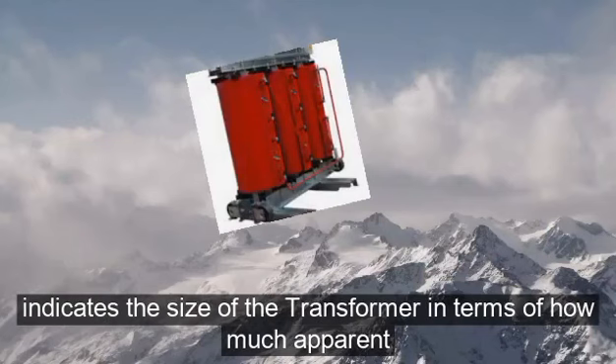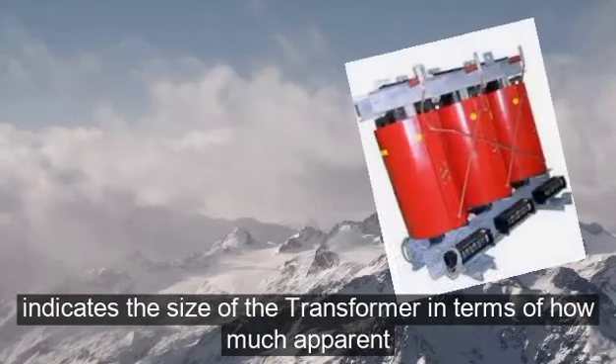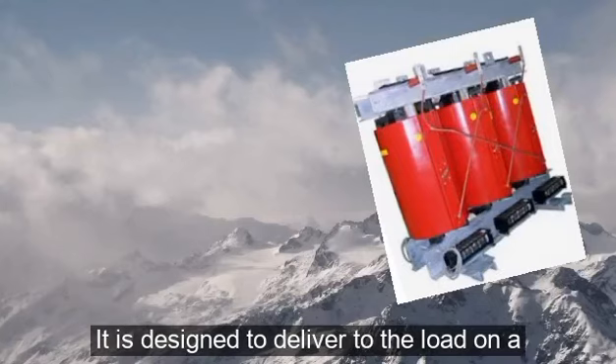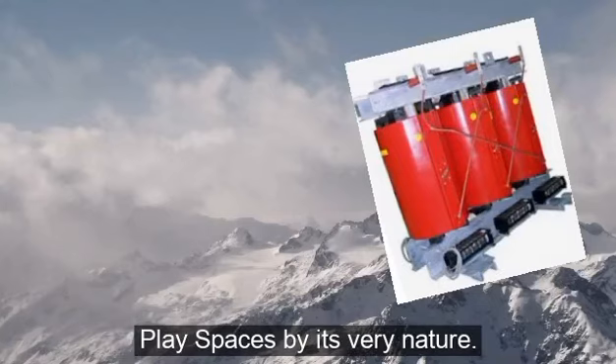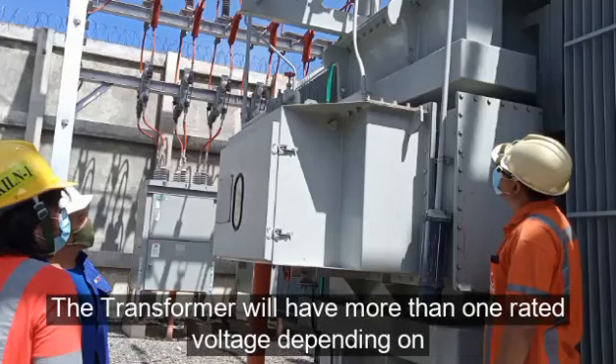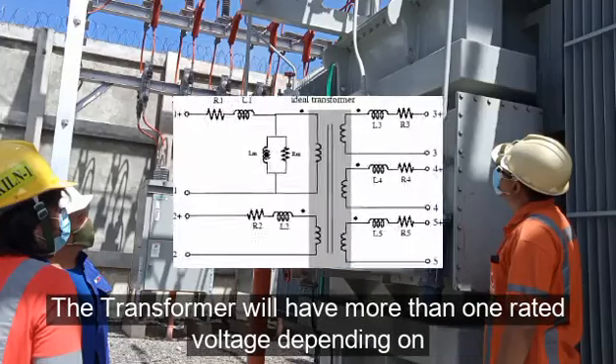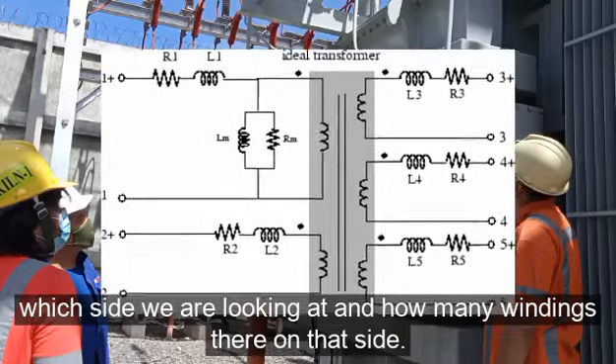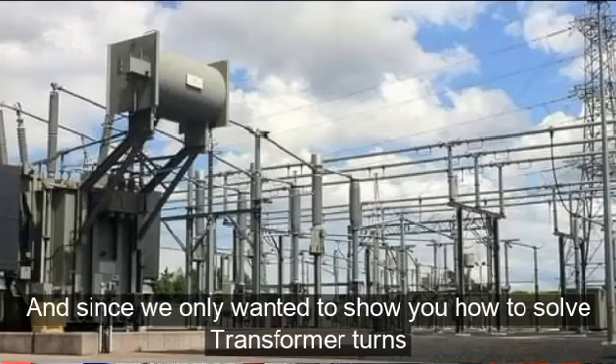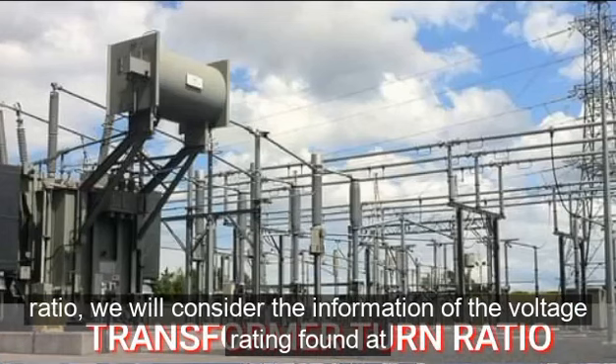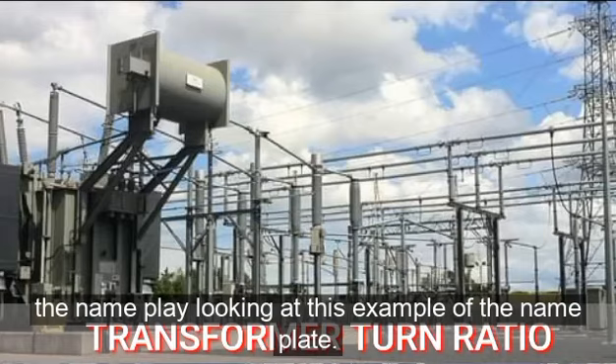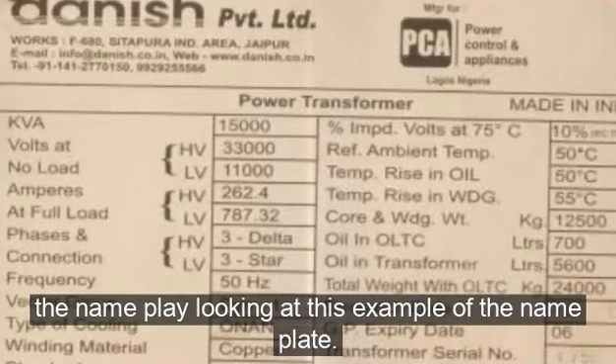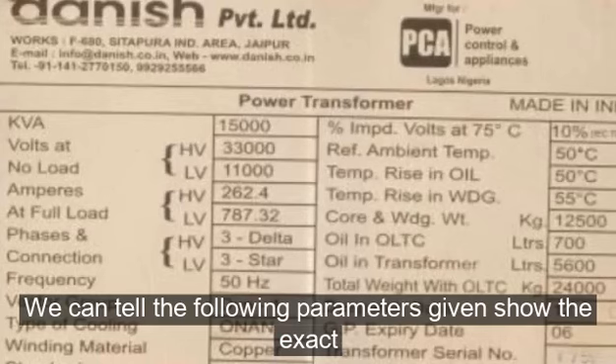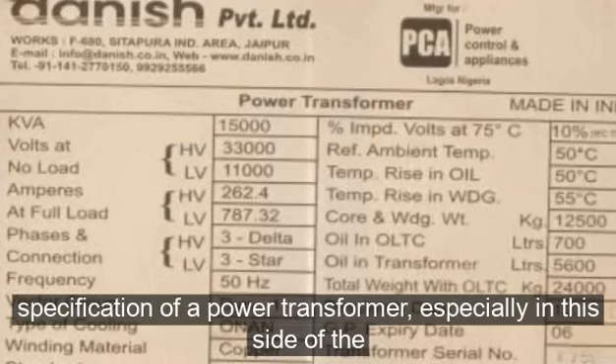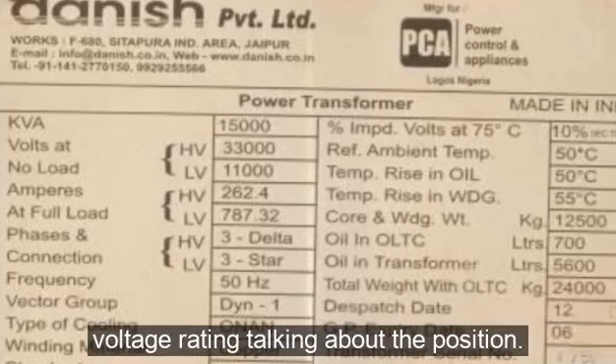The nameplate always indicates the size of the transformer in terms of how much apparent power, rated kVA, it is designed to deliver to the load on a continuous basis. By its very nature, the transformer will have more than one rated voltage, depending on which side we are looking at and how many windings there are on that side. Since we only want to show you how to solve the transformer turns ratio, we will consider the information of the voltage rating found on the nameplate. Looking at this example of the nameplate, we can tell the following parameters given, showing the exact specification of the power transformer, especially on this side of the voltage rating.